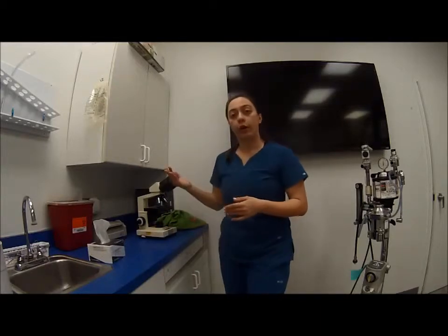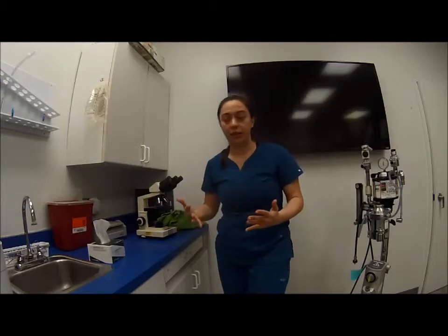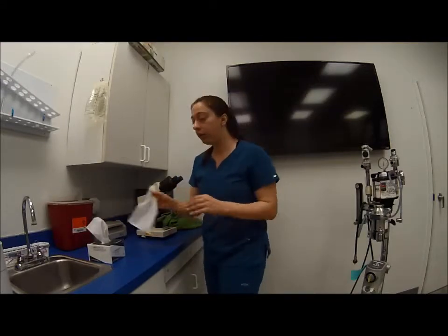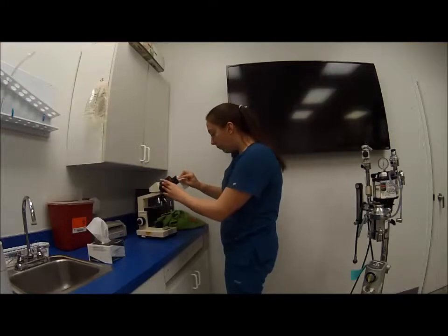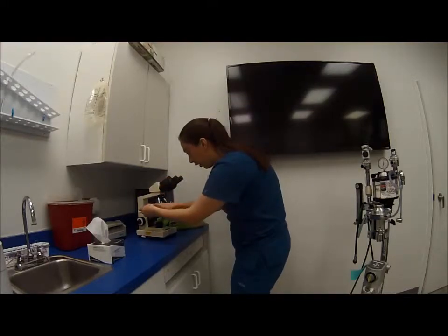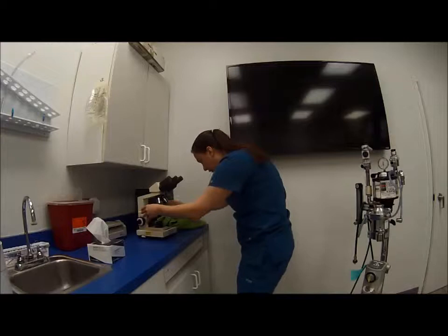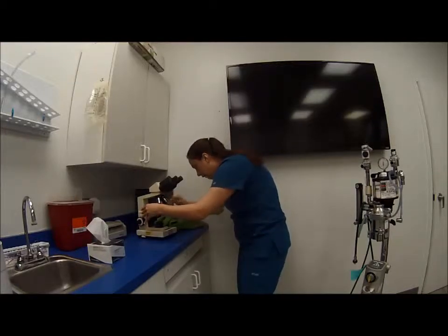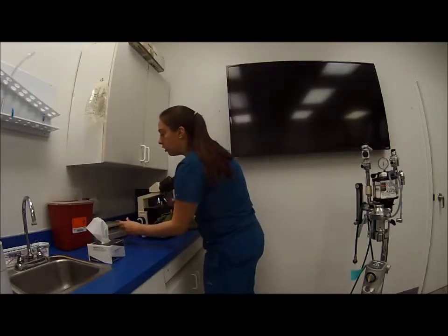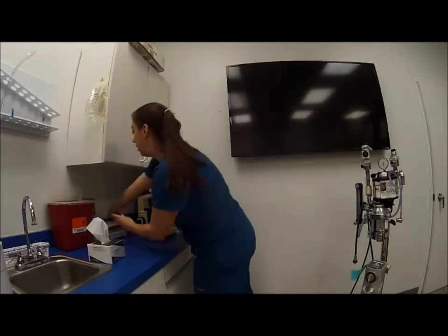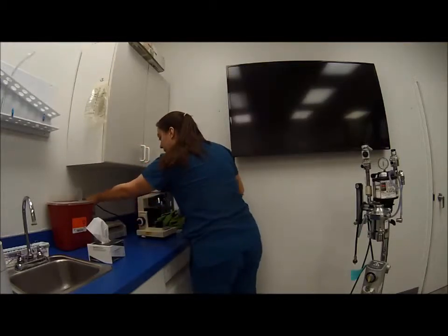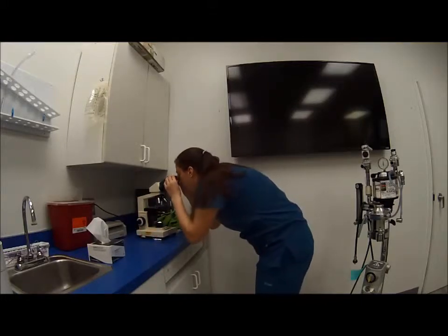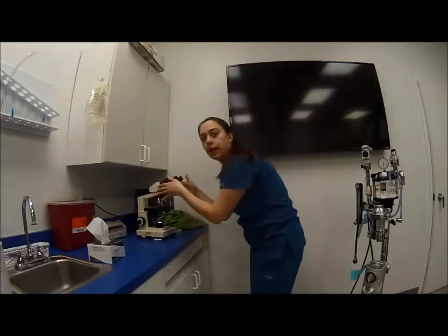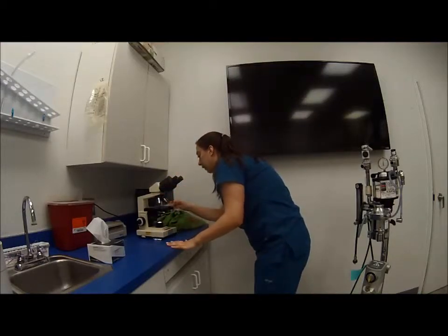When you're using the oil for the immersion lens, if there's excess oil on the lens, you can use xylene. So we have our wipes here, and you want to wipe the eyepiece, the stage, move this around so you can make sure you get all the dust off. Carefully clean the lens. And then you can check to make sure if there's any debris in the eyepiece. You can turn it on and move each eyepiece separately, and if any debris moves, you know that it's inside and you have to clean that off.